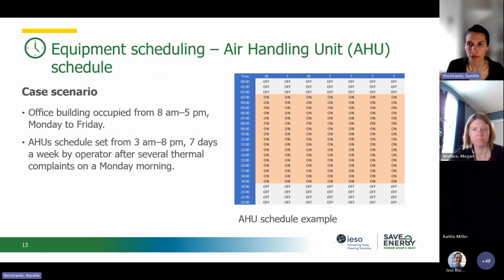In the first scenario we present here, we are in an office building occupied from 8 a.m. to 5 p.m., Monday to Friday. And during the investigation, you see that the air handling unit schedule is set from 3 a.m. to 8 p.m., 7 days a week. After discussion with the operator, the schedule was originally set to 6 a.m. to 5 p.m. Monday to Friday, but the schedule was modified maybe 2 years ago during winter when tenants complained about thermal comfort on a Monday morning, for example, minus 20 degrees C outdoor, and it was just left like that.